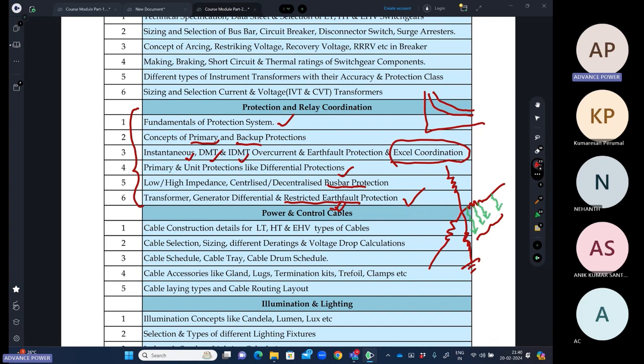So why this terminology? What are the differences between high and low impedance? Where do we use the stabilizing resistance, metrosil? So all those calculations: CT parameter calculation, CT saturation, knee point voltage calculation, magnetizing current of CT calculation. So everything we'll discuss here.